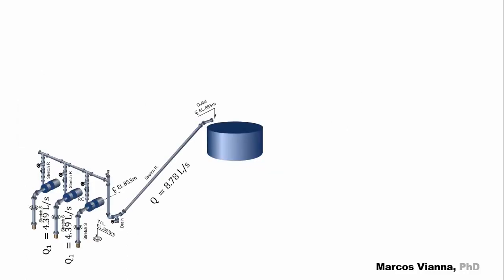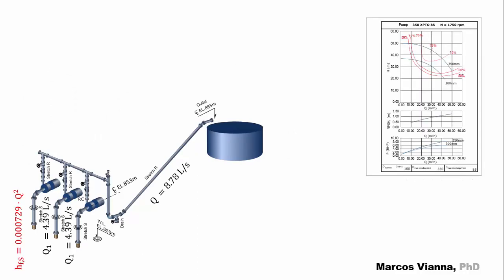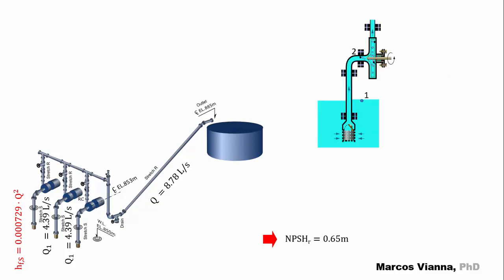Okay, now this is the system that we are studying. Two pumps that run in parallel and a third one on standby. We know the pump chart and the contribution of each one of the pumps. That will be half of the total flow. For this contribution, we found that the corresponding required NPSH was 0.65 meter. Now, this is what happens at the suction of each pump.